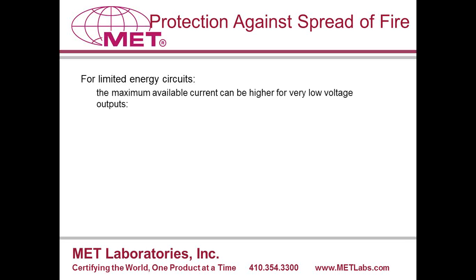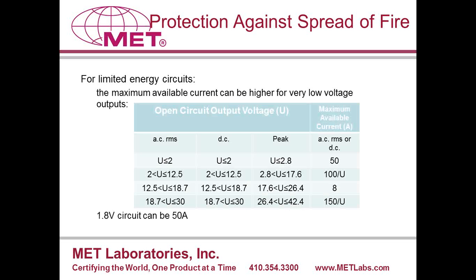In the 3rd edition standard, there is recognition of a very low voltage circuit, such as a 5-volt or 3.3-volt circuit, which may have substantial current but not enough to cause a fire. The standard now has created new categories for these low voltage circuits, and the current limits have been raised. For example, as seen in the first row, a 1.8-volt circuit can now have 50 amps going through it and not be considered a fire hazard. As seen in the second row, a 5-volt circuit can have up to 20 amps through it as well.